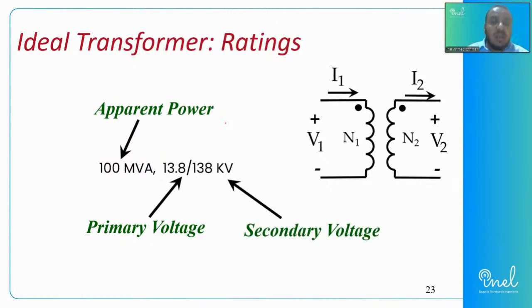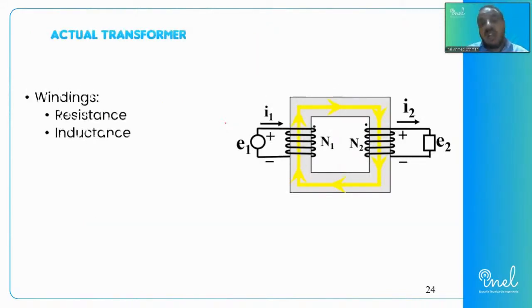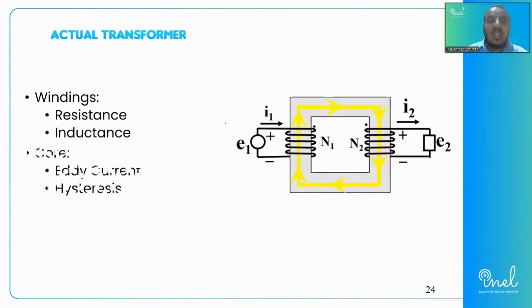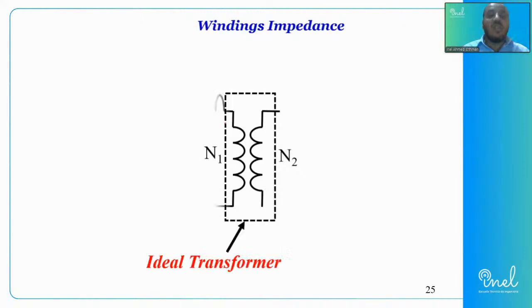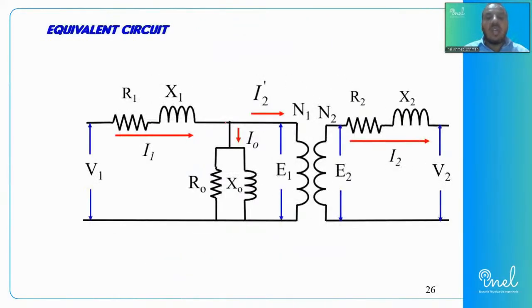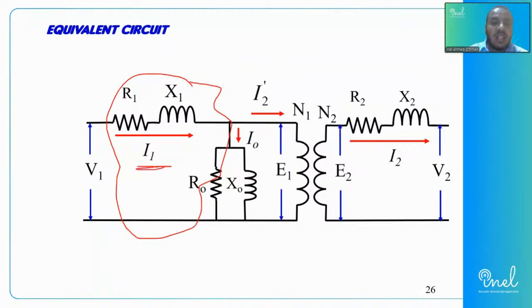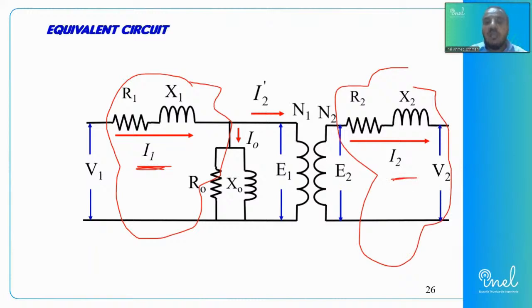And how do we describe the rated values? We have the rated apparent power, the rated primary voltage, and the rated secondary voltage. How do we describe any transformer based on the winding and based on the core, where the core has some eddy current and hysteresis losses? So here is the equivalent circuit of the transformer. When we apply differential protection, we will differentiate between both currents. Here we have the primary current and the secondary current, and we should keep no differential between them, given the turns ratio between them.